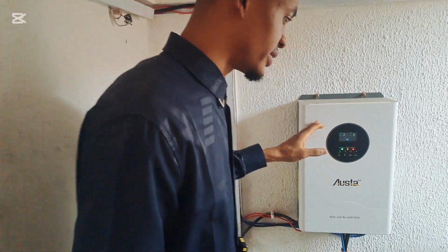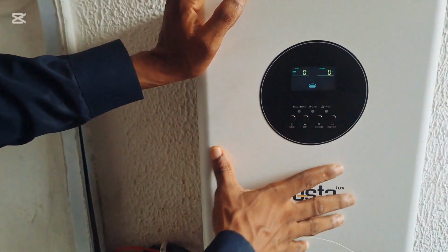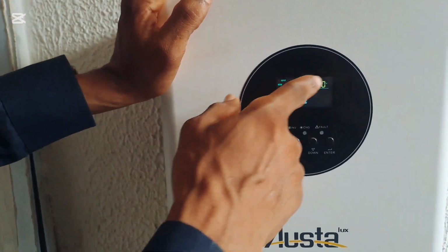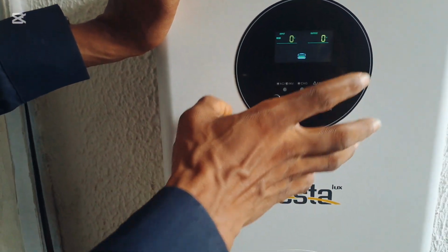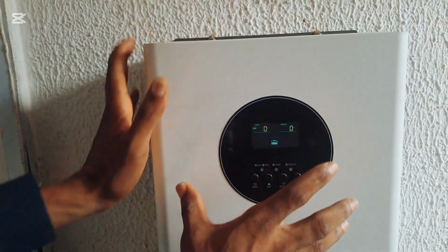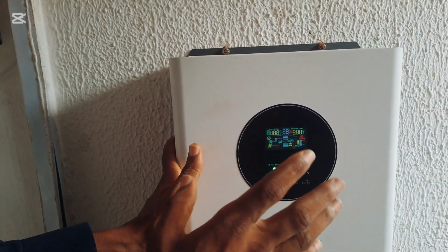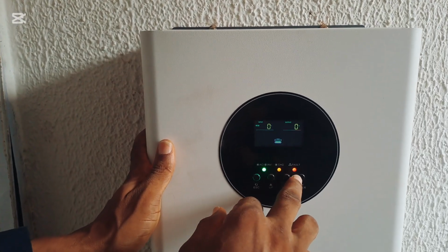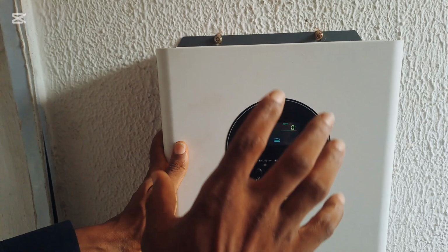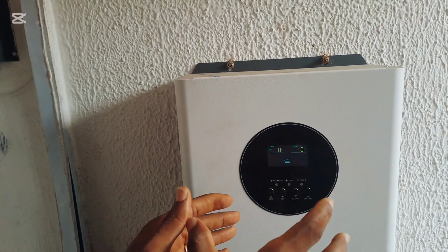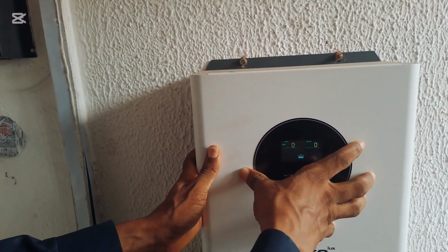Look at this inverter now. If you look at this system, you can see that there is no input and there is no output. If you go further, you see that the screen sometimes goes blank, meaning that there is a battery existing. Just like you can see, it is indicating a fault. This is indicating a fault, but it is not a fault per se. This simply means that there is existence of a battery and the battery is at a low state.